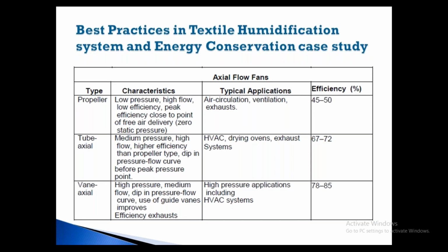There is a very good scope for changing fans to vane axial fans, because in vane axial you have a guiding vane on the head side or tail side of your fan. So it will guide the air movement without turbulence, smooth movement of air. When it guides, the efficiency improves.